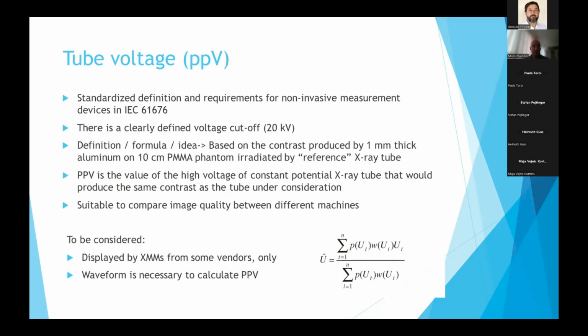So the first quantity is practical peak voltage. It is very important for calibration laboratories because it is standardized. So IEC 61267 uses practical peak voltage, and there is also a definition in IEC 61676. And you can find standard requirements for non-invasive devices measuring practical peak voltage. Also, radiation qualities that are used for calibration of user equipment use practical peak voltage. So this quantity is very commonly used in calibration laboratories, but our surveys show that the end users, the clinical medical physicists, very rarely use this quantity. So this is a downside.